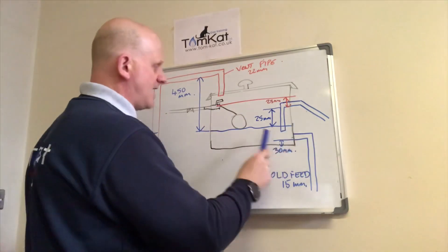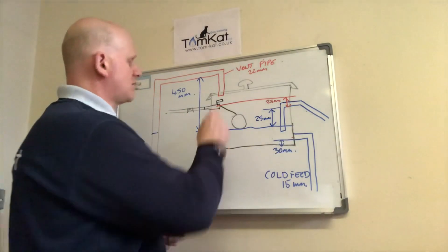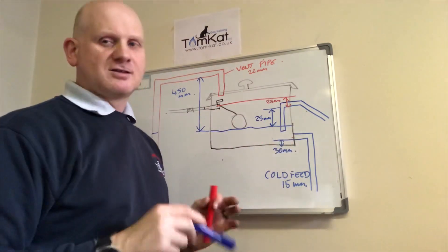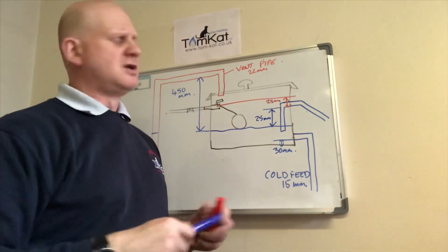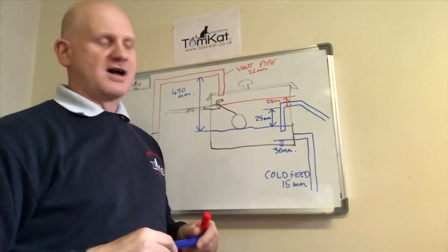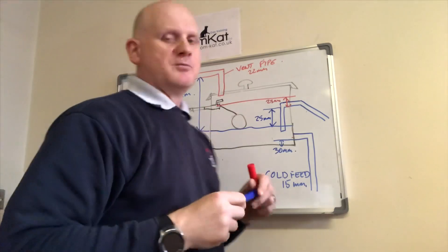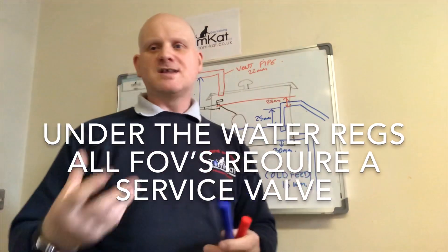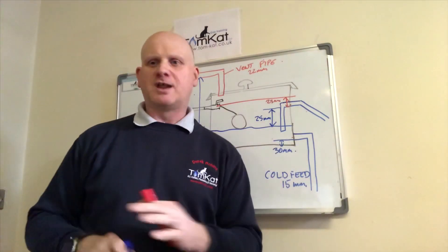While we're talking about the FOV, it's always better to put the outlet at the opposite end to the inlet, because as water is filling in, it creates air bubbles, and putting the outlet at the far end allows that air to run out. If this was a feed system, we wouldn't get stagnant water - we'd always get water coming in and running out. It's always best to put our outlets at the opposite end to our inlet. Again, we've got a close fitting lid and the vent on top. On the FOV we need an isolation valve. On the cold feed we don't put an isolation valve - because this is where the expansion comes in, this is where the water expands.